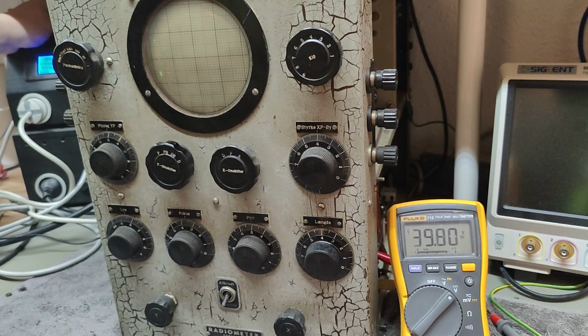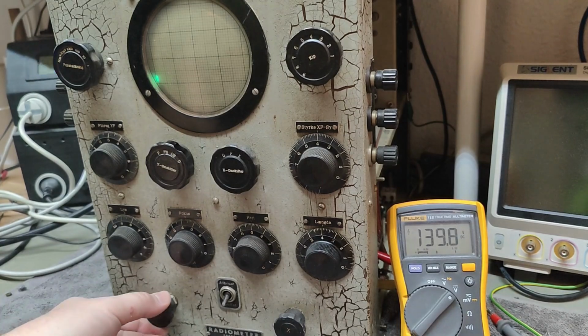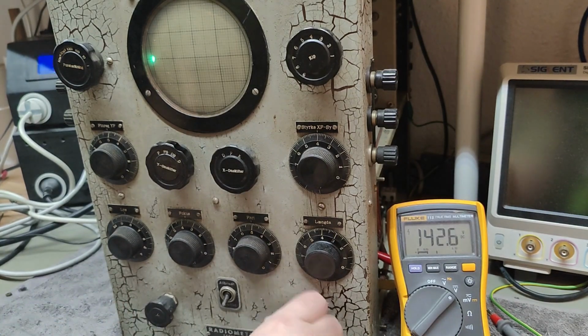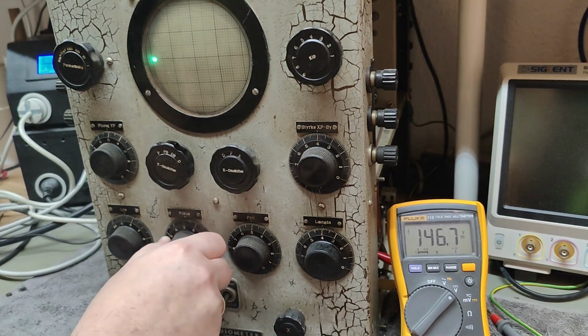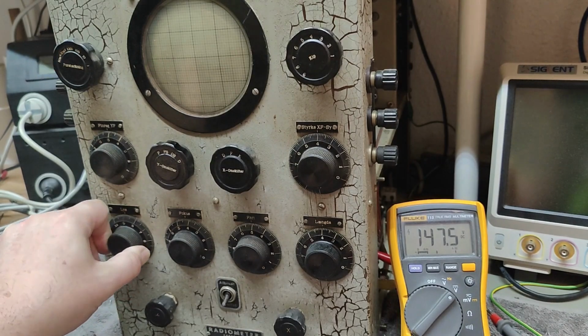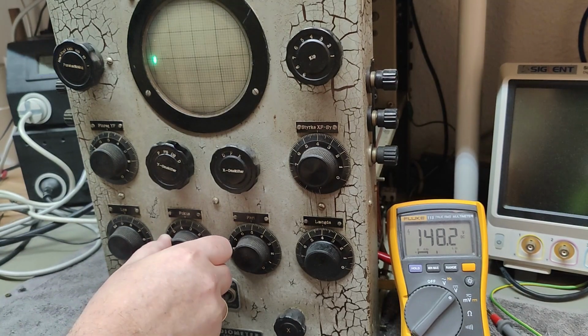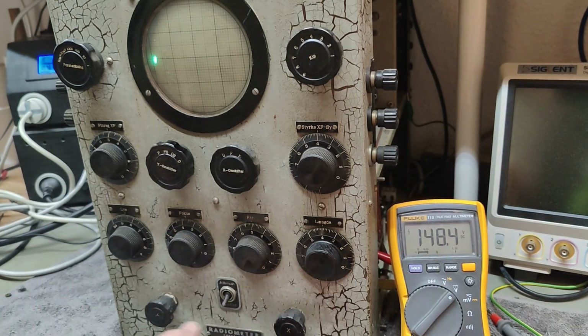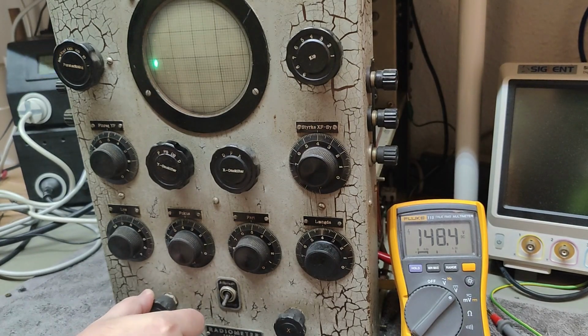Look at that, it is getting higher and higher. And here is 210 volts, and it's using 105. We have position here is working. Not much position of the other one. This reveals we have a problem with this system. Focus, light, is at maximum. Our supply is still only 148 volts, so that explains why this position here is not working. Yeah, I better turn it off.